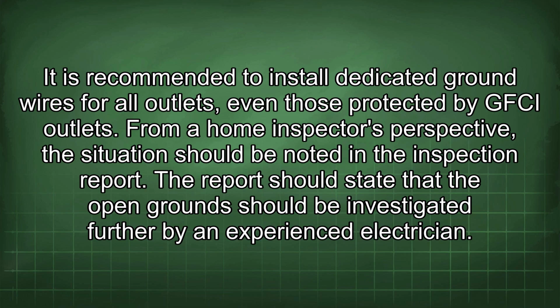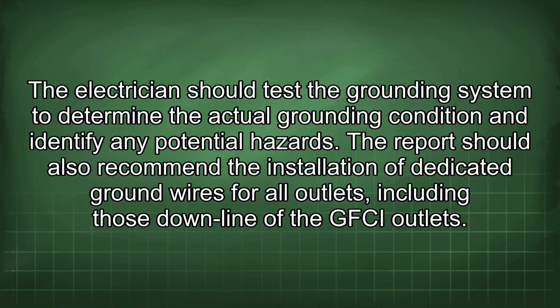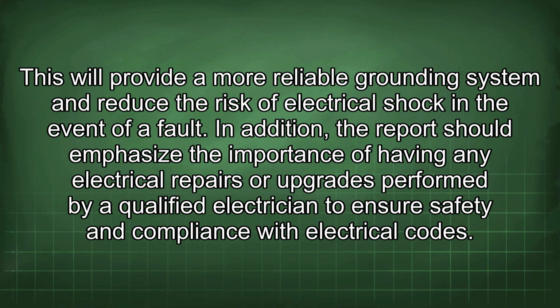From a home inspector's perspective, the situation should be noted in the inspection report. The report should state that the open ground should be investigated further by an experienced electrician. The electrician should test the grounding system to determine the actual grounding condition and identify any potential hazards. The report should also recommend the installation of dedicated ground wires for all outlets, including those downline of the GFCI outlets. This will provide a more reliable grounding system and reduce the risk of electrical shock in the event of a fault.